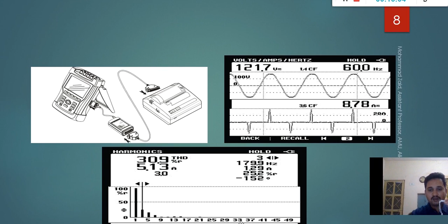Suppose you see this kind of waveform which you get from a harmonic analyzer. This is the waveform of a voltage, this is the waveform of a current, and they are showing the harmonics. Sorry, in the current they are showing a THD of 30.9%, and for 3 ampere current, 5.13 ampere is there, and the maximum frequency and all those things are shown here.